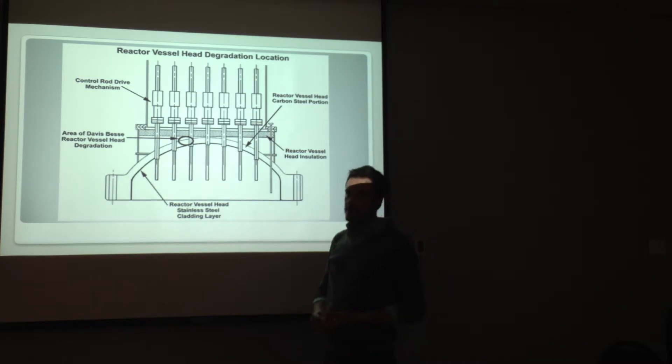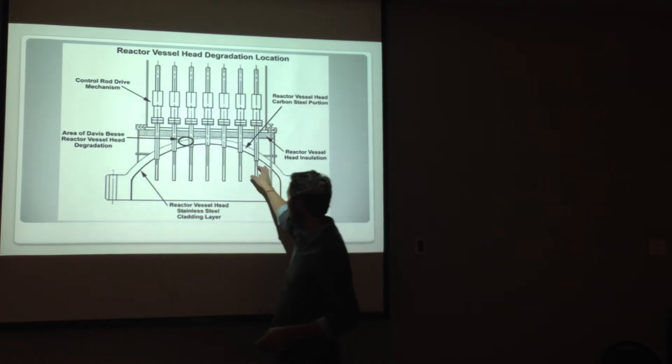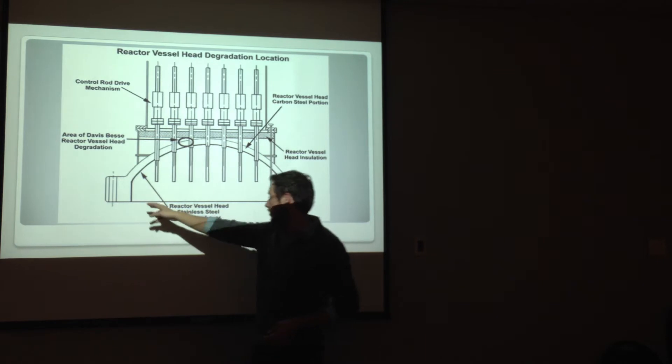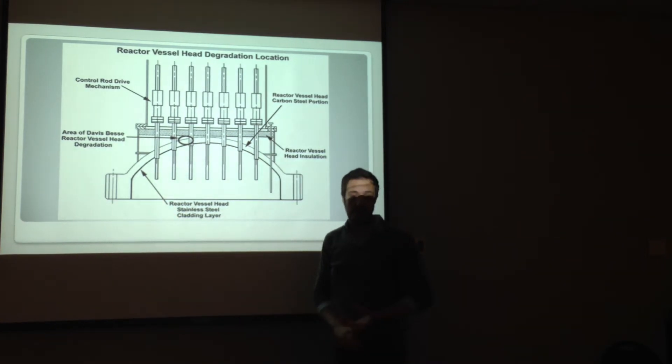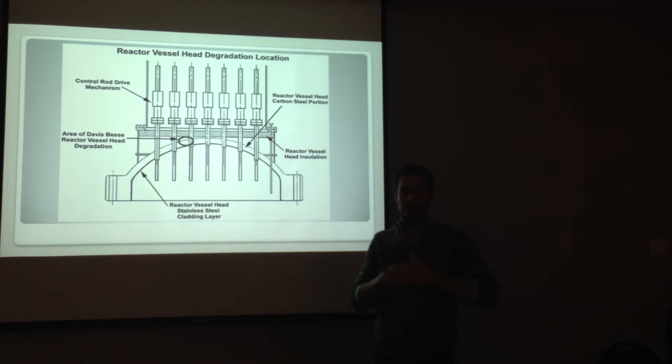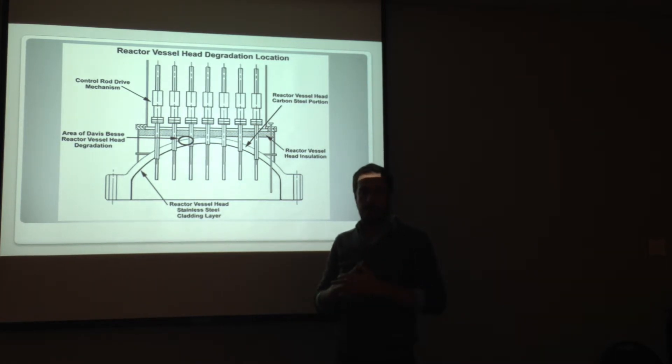And subsequent ultrasonic testing, eddy current testing, stuff like that that's non-invasive and non-visual wasn't done far enough down to indicate that there was leakage there. So, inside this primary system there's this layer right here, this black line of stainless steel cladding. It's only about three-eighths an inch thick but it's basically a boundary in between the primary water and that carbon steel to prevent the boric acid from corroding.